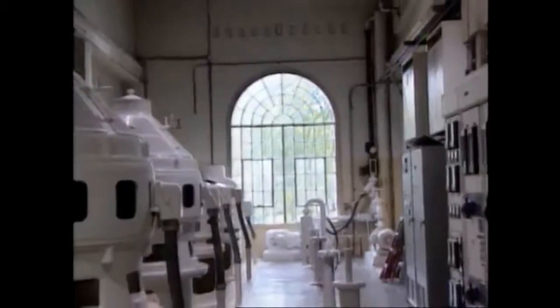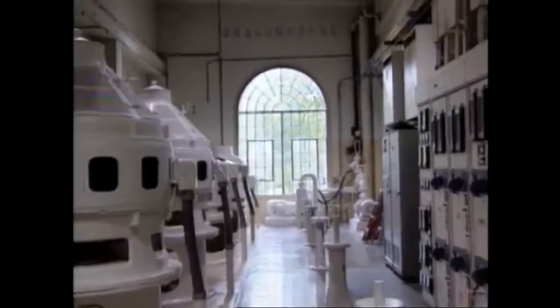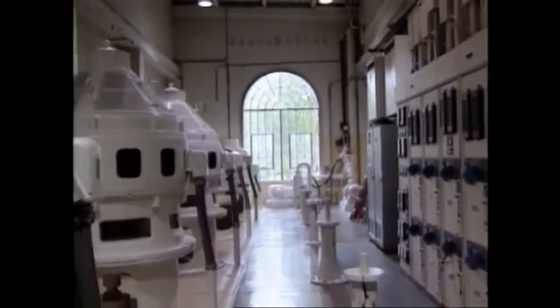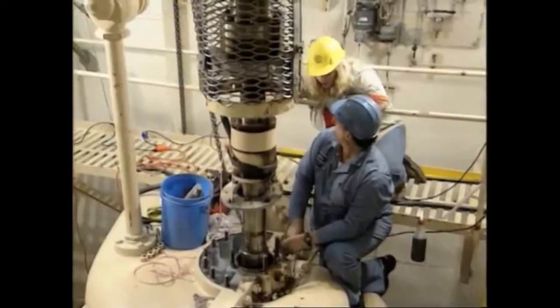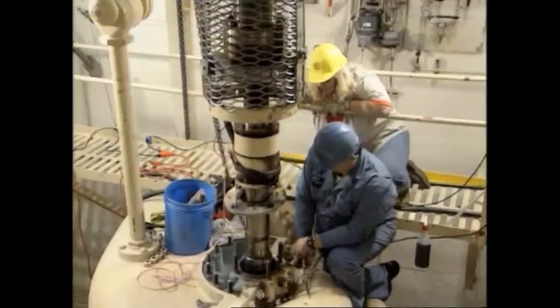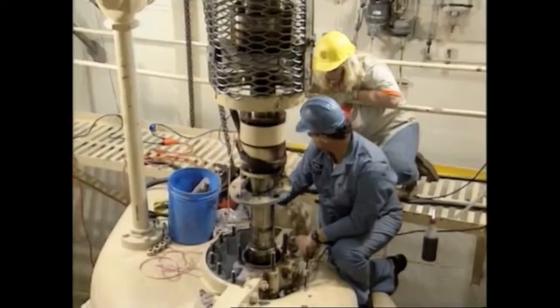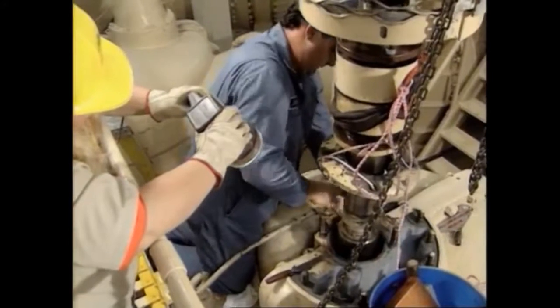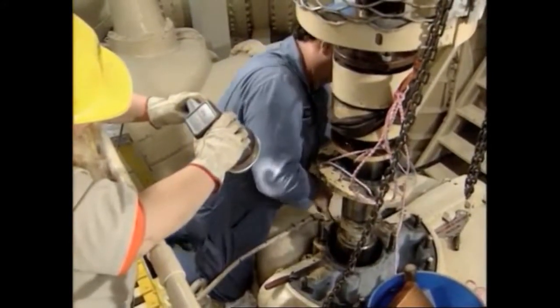Pumps are used to move wastewater in collection systems when a gravity system is not feasible or is too costly. In the collection system, pumps are used in the lift stations to move water from lower elevations to higher elevations. Packing is probably the single biggest problem for the maintenance operator maintaining pumps. More pumps have been damaged due to improper maintenance of packing than for any other reason. Packing a pump is very important.